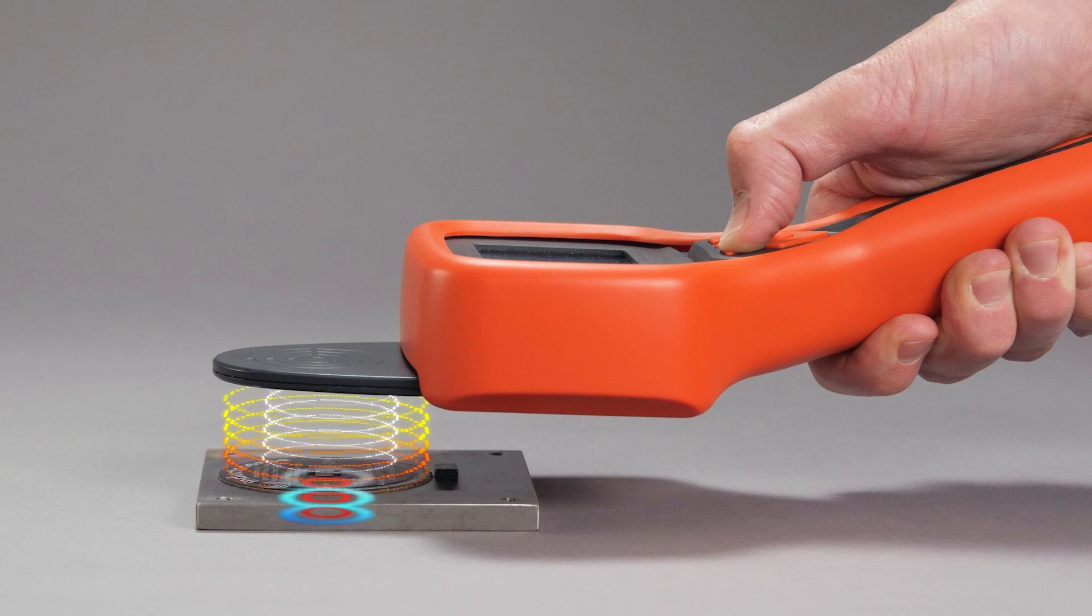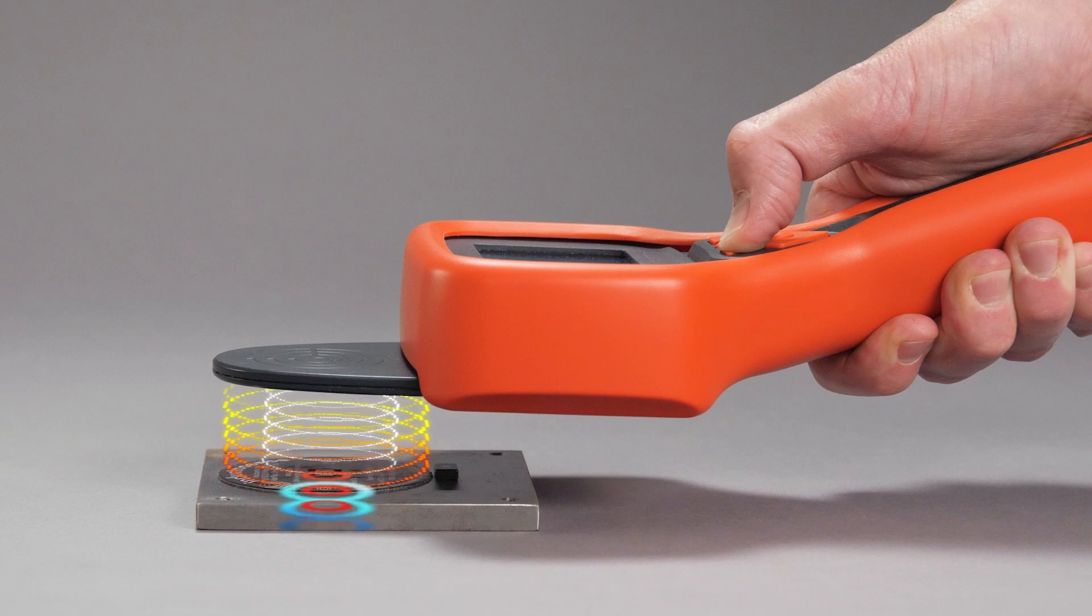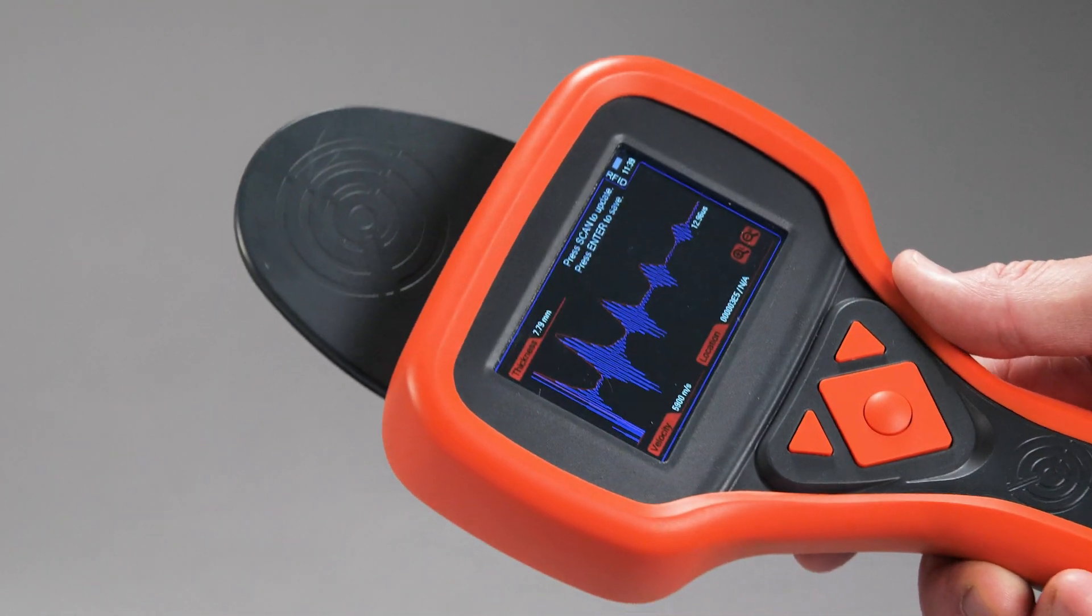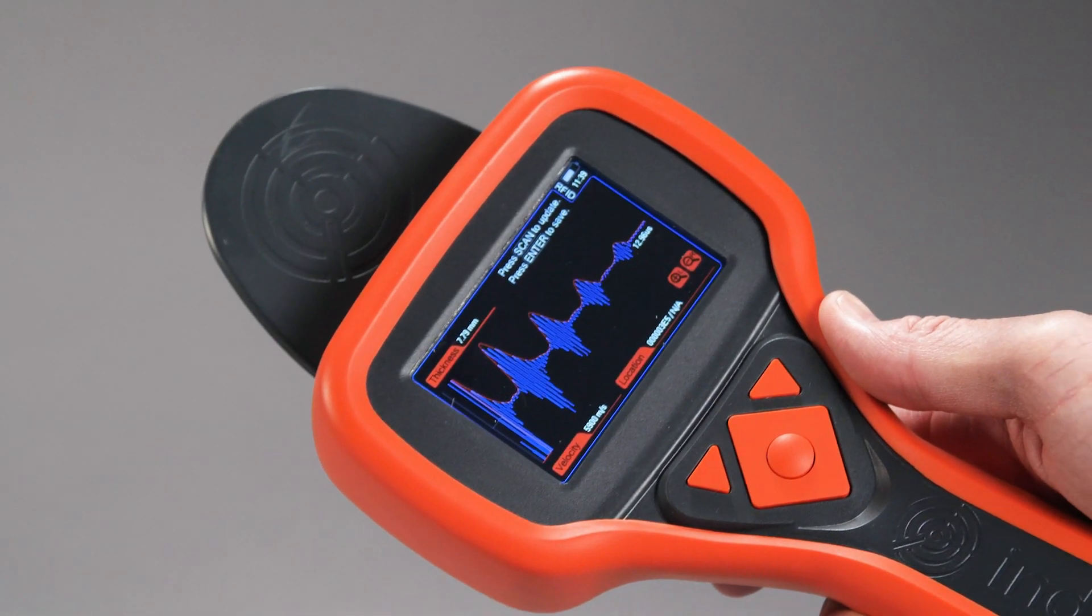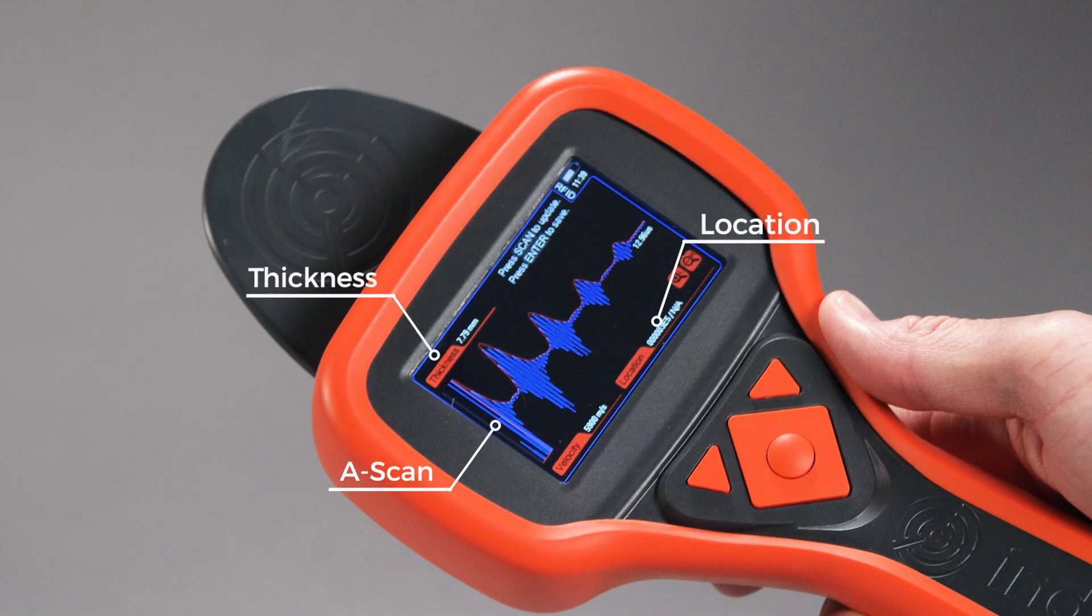At the same time, the installed sensor transmits an ultrasonic signal into the structure and receives the scattered signal. This information is coupled back to the data collector where the ultrasonic A-scan is displayed on the screen along with the thickness of the structure and the location of the sensor.